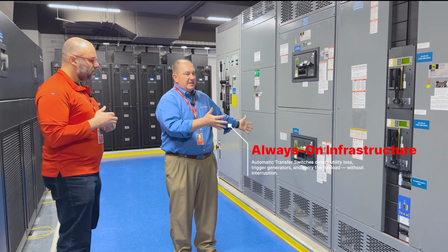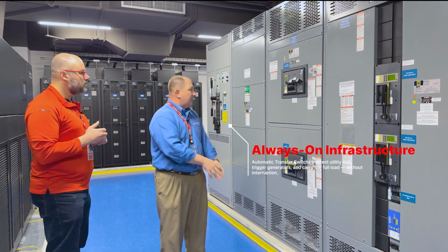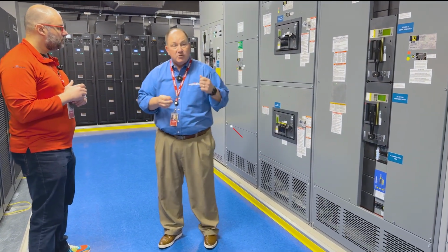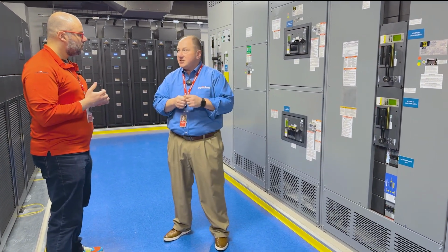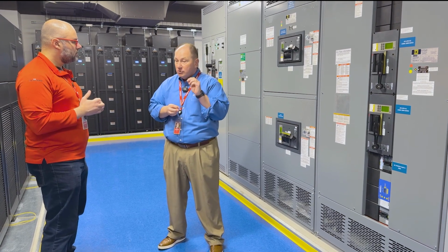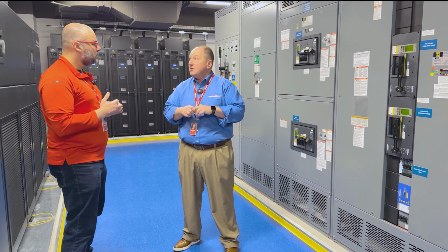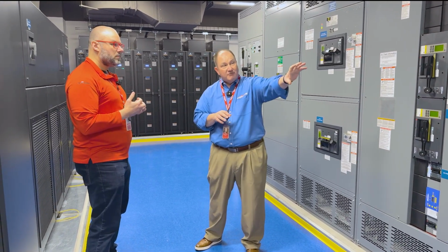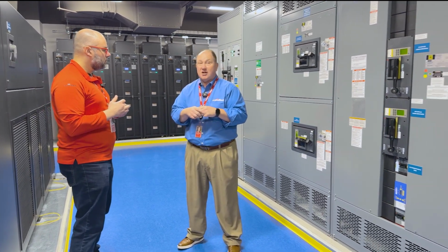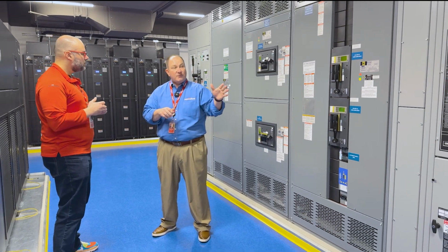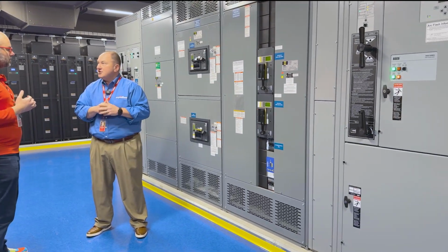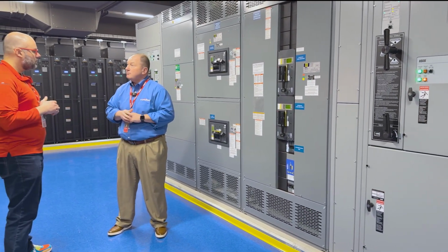This is all the mains coming in from the utility company, and on the ends we're framed by our transfer switches. The transfer switches control the transition of power from normal commercial power to the emergency generators. These devices sense a loss of commercial power, send a signal to the generators to start, and then transfer all the load over to the generators. The generators carry it until commercial power comes back.